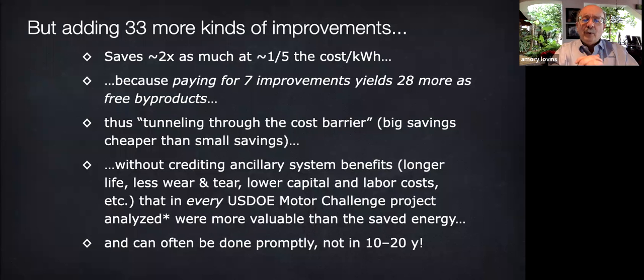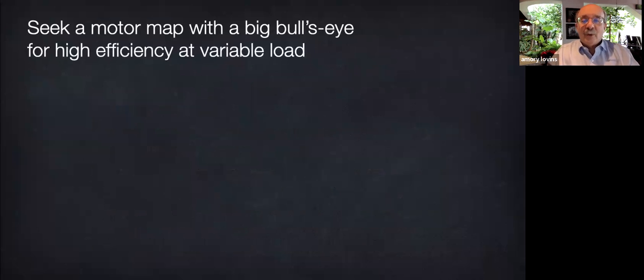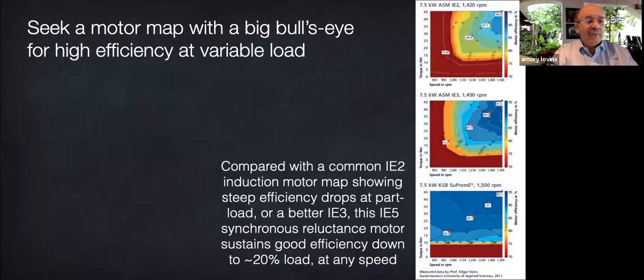But this view counts just one benefit, direct electrical savings based on the higher nameplate efficiency of the new motor measured at its full rated load. It ignores 17 other benefits. What are those extra benefits? Well, first, few motors actually run at or near their full rated load, and that part loading can greatly reduce their efficiency.